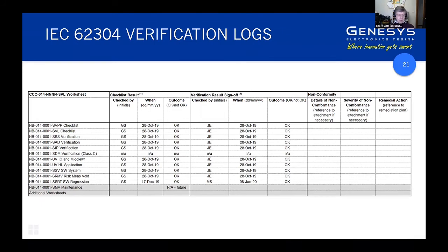And finally, whenever we do updates, we need to do software regression testing and verify that. There is a whole separate set of requirements in the maintenance phase for verifying software updates. In this particular document that was not applicable, but when you get into software maintenance after the product's on the market, you have another whole heap of requirements that come into play.